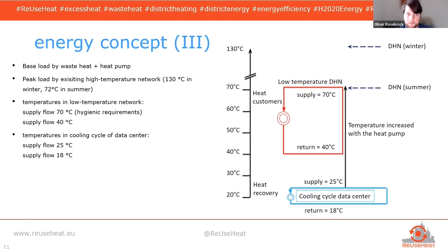This still quite high temperature of 70 degrees C in the supply flow is caused by the hygienic requirements. So we have the topic of Legionella, which leads us to have at least 60 degrees C in the heating systems to avoid Legionella problems. And therefore, the supply flow temperature needs to be higher than this. And 70 degrees was the value chosen here. This was especially because we also wanted to deliver domestic hot water, not only space heating.